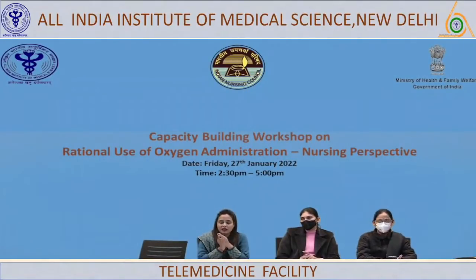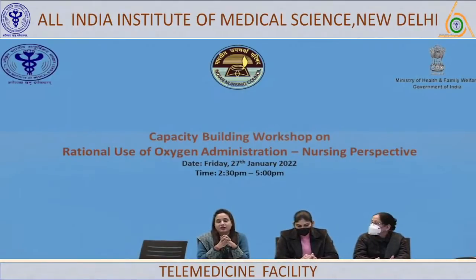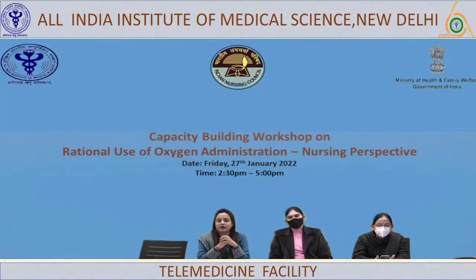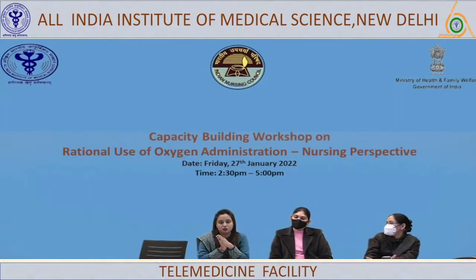Yes. And if we are using the reusable one, it needs to be disinfected at least every 72 hours if it is being used for a single patient. And once we are moving from one patient to another, they need to be disinfected. Now, how to disinfect them? We need to wash them with water and detergent first, rinse the detergent completely and dip them in 2% glutaraldehyde or Cidex solution for at least 30 minutes. Whoever is disinfecting needs to make sure that the disinfectant enters the lumen of the tubing completely. Once 30 minutes are over, we can take them out of the solution, rinse them again with sterile water, air dry them and keep them ready for the next use. As nowadays we are considering each and every patient as infected, we need to be very particular. Whoever is disinfecting needs to wear proper PPE while disinfecting these devices.